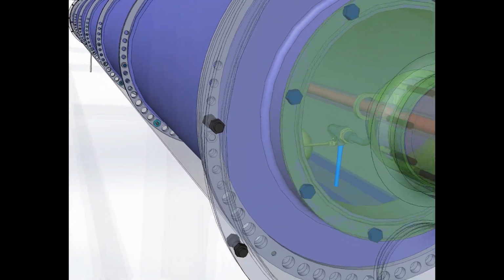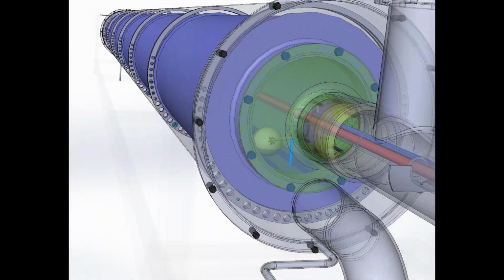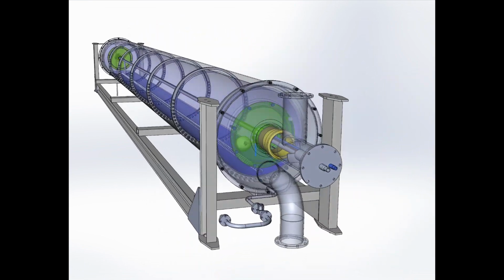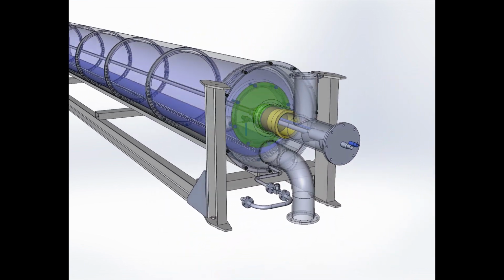Another factor that ensures a high bearing life is the material from which the bearings are made. This is ceramic that is highly corrosion resistant and does not require lubrication. Pure water vapor conditions are ideal for the operation of these bearings, ensuring low mechanical losses when the drum rotates.